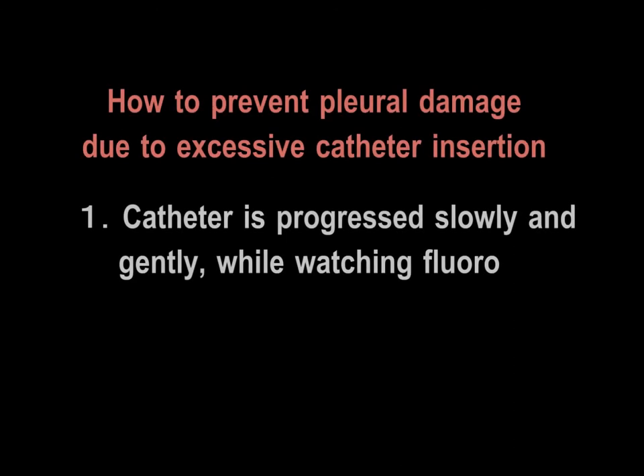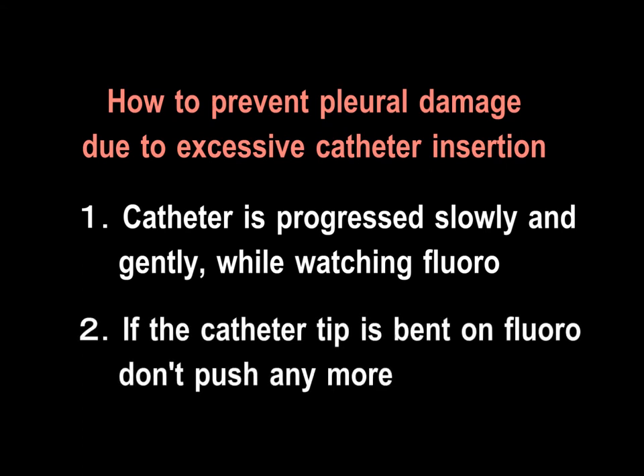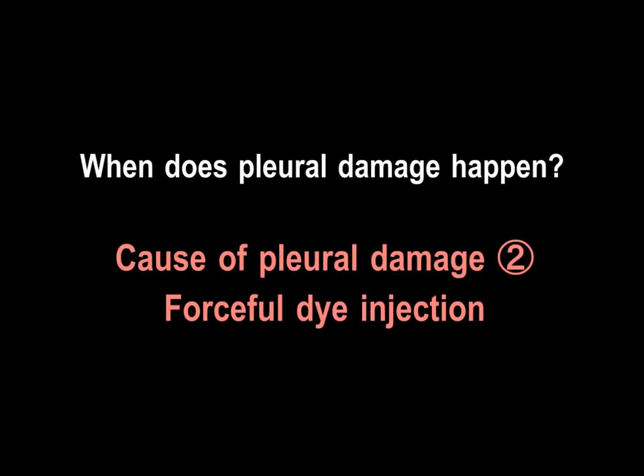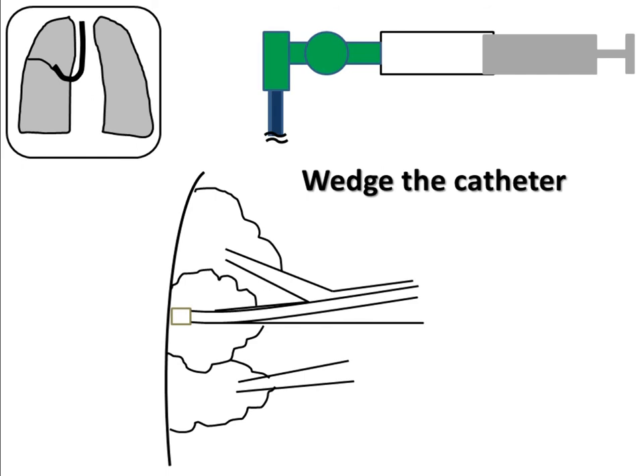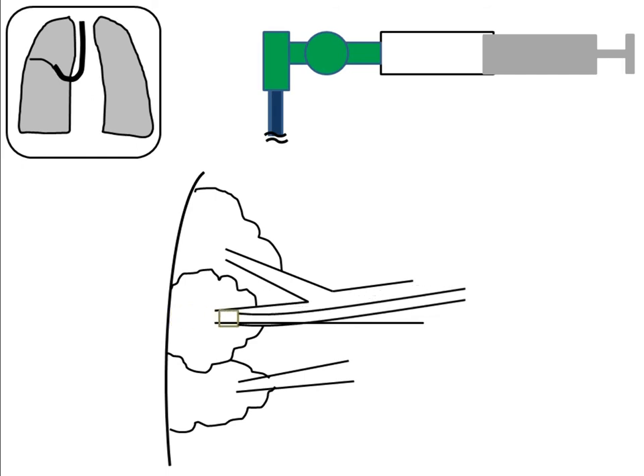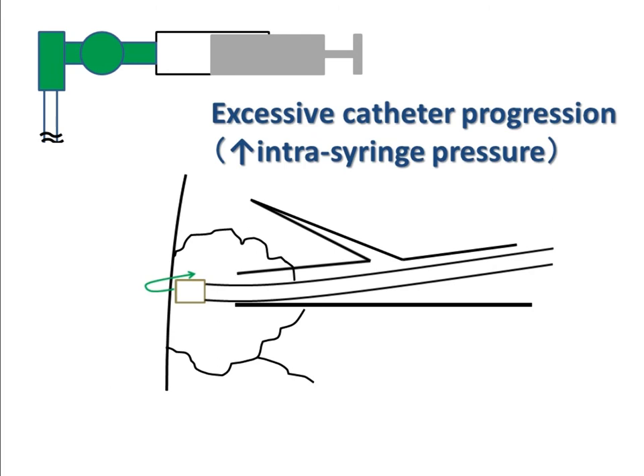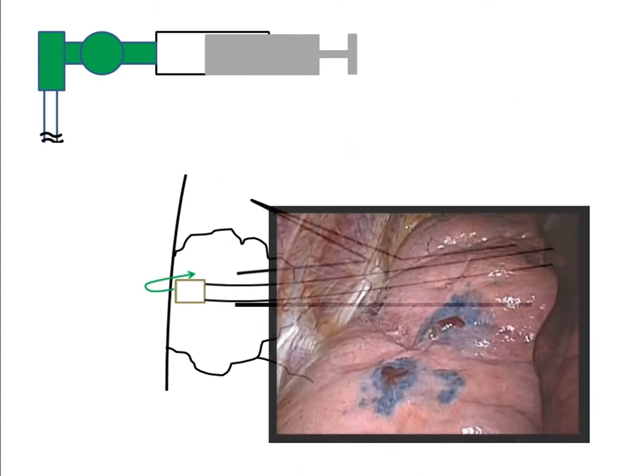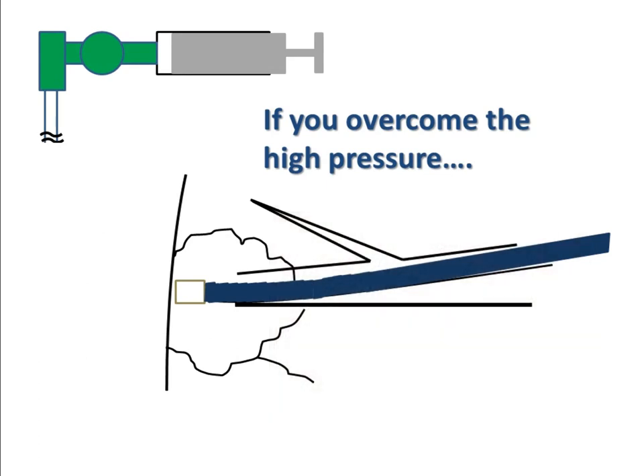It's always dangerous. How can we prevent pleural damage due to excessive catheter insertion? The catheter should be progressed slowly and gently while watching the fluoro screen carefully. If the catheter tip appears bent on the fluoro screen, you should not push it anymore. That's very dangerous. Here is shown the second mechanism of pleural damage, that is forceful dye injection. So here's the animation again. First wedge the catheter and then withdraw it little by little, and at some point you can push the plunger of the syringe. At that moment you push the catheter a little bit, but if you do it too much against a high pressure, then of course that could cause damage to the pleura as shown in the picture.